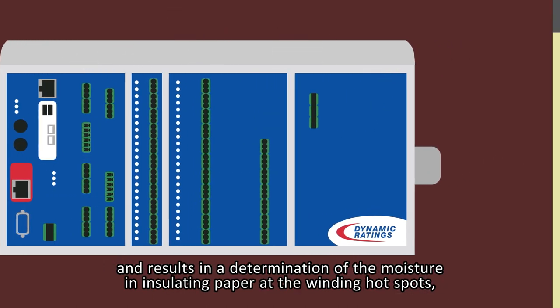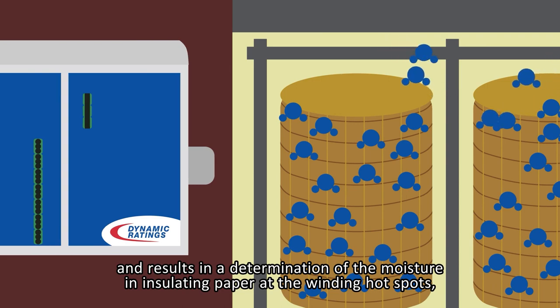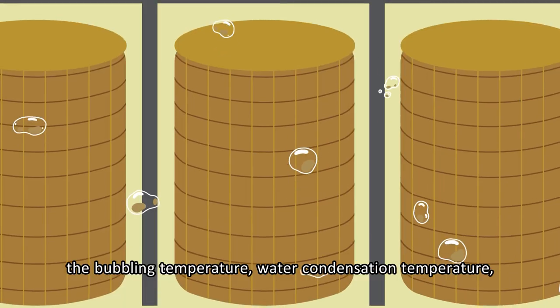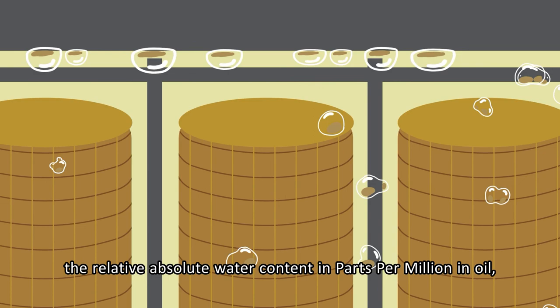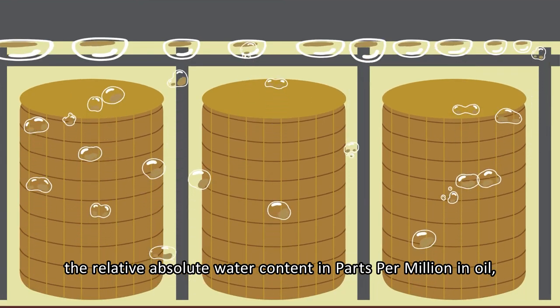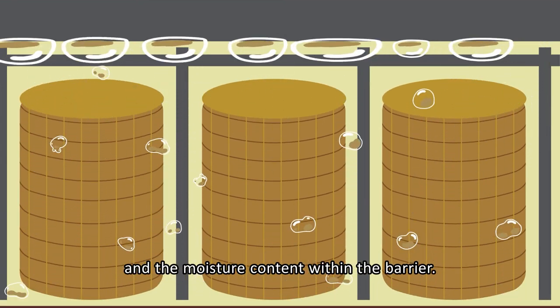The transformer monitor applies various rules to the data and results in a determination of the moisture in insulating paper at the winding hotspots, the bubbling temperature, water condensation temperature, the relative absolute water content in parts per million in oil, and the moisture content within the barrier.